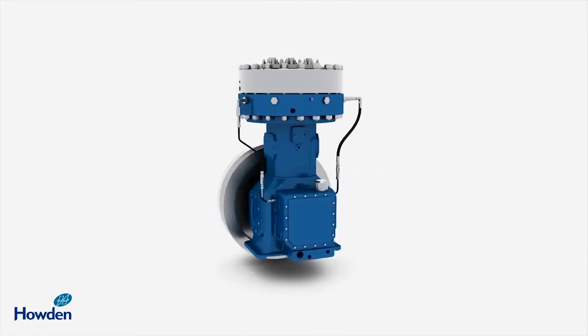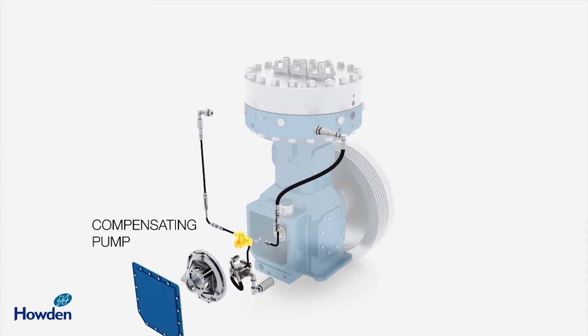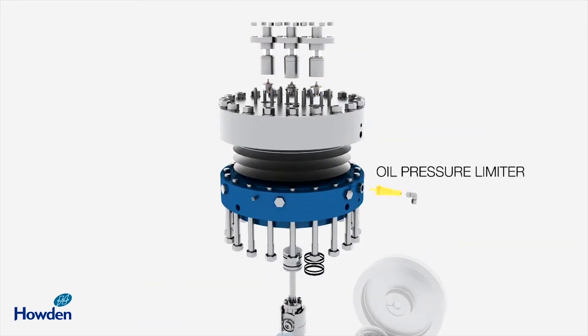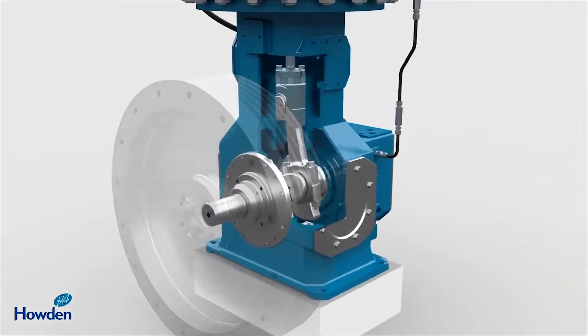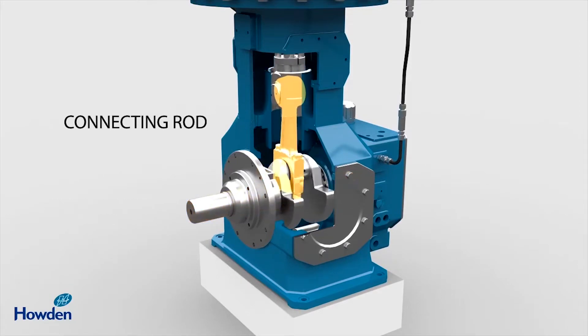In a wastewater treatment operation, diaphragm compressors are often used to convert low-pressure gas or liquid to high pressure through a flexible membrane, typically used in situations where complete hermetic separation is required. The compressors often handle toxic, flammable, or explosive gases. In our case, this compressor injects oxygen into sedimentation tanks to accelerate microbial sanitation processes.